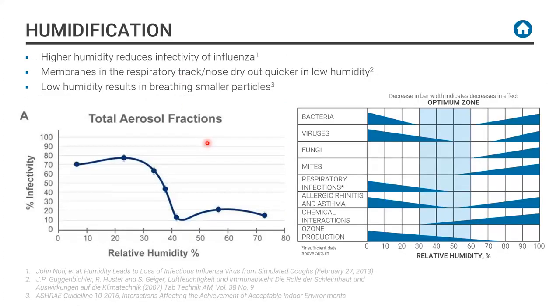We all know when we get sick: we get sicker in the wintertime than in the summertime, especially in cold climates. The reason, first of all, is that high humidity reduces the infectivity of the flu virus. This is a chart of infectivity versus RH for the flu virus, and if you remember, I said before that SARS-CoV-2 mimics this. From 10 to 30% RH the flu virus is very, very active, but the minute it gets to 40 to 60%, it becomes less active. They used an MS2 virus, which mimics the SARS virus, and found that the half-life of the virus at 20% is three times what it is at 40%, so it lives longer. So that's factor number one.